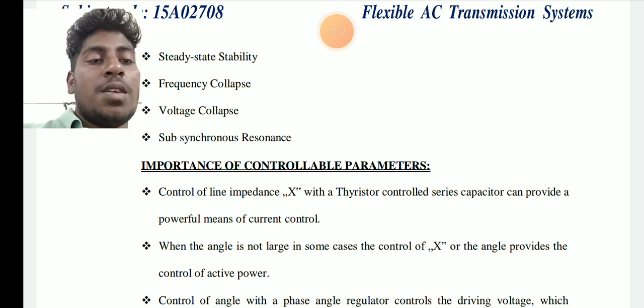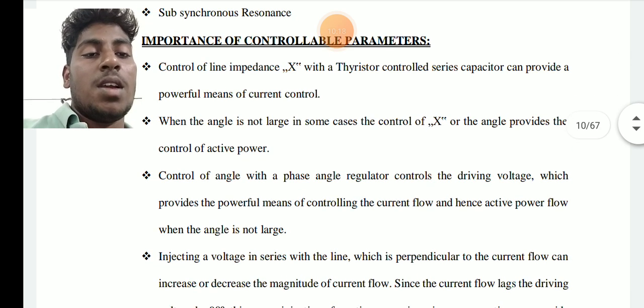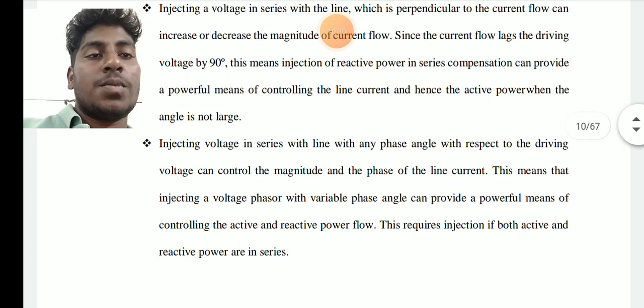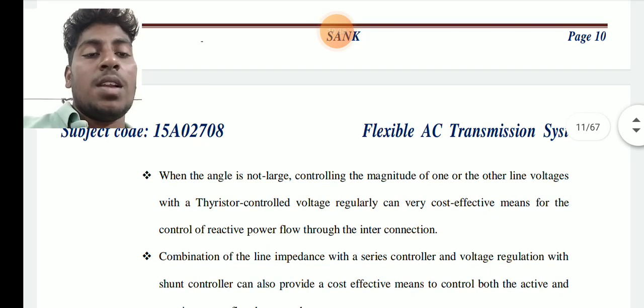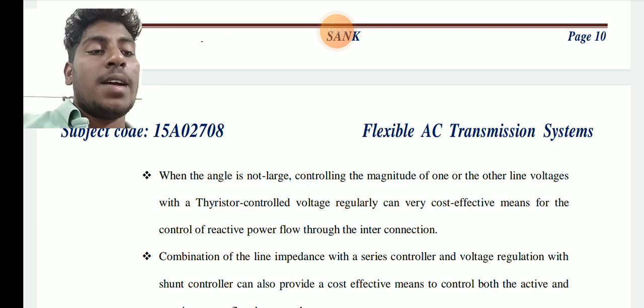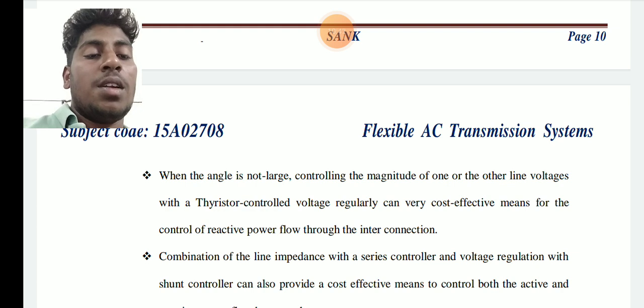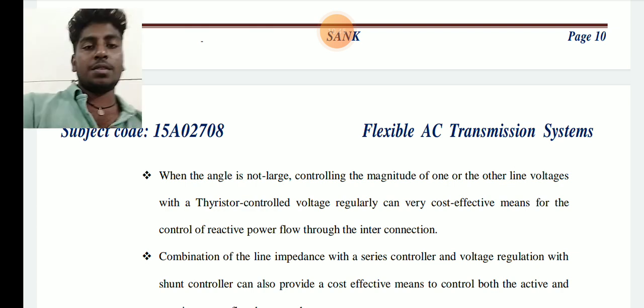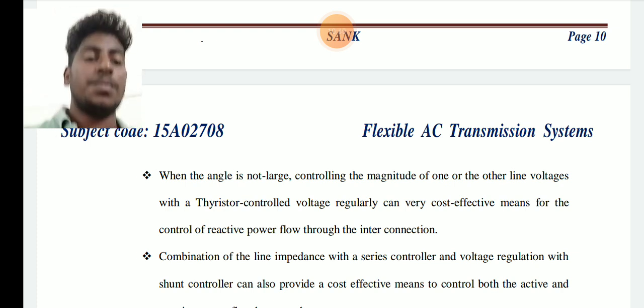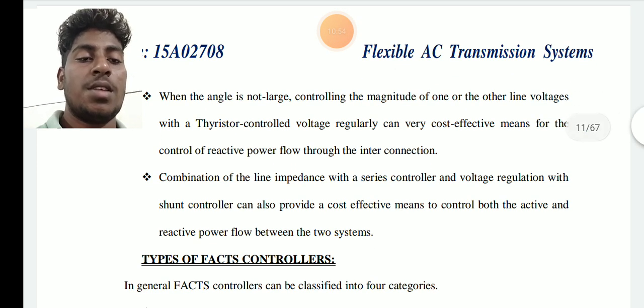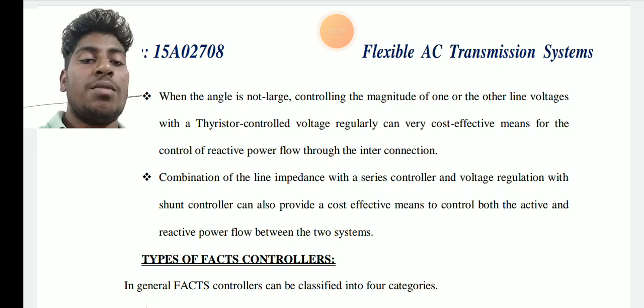Once I repeat, importance of controllable parameters. Controllable line impedance X with thyristor controlled series capacitors provides a powerful means of control. When the angle is not large, in some cases controlling X and the angle provides control of active power. Control of the angle with a phase angle regulator, and control of the driving voltage, provides a powerful means of controlling the current flow and hence the active power flow when the angle is not large. When the angle is not large, controlling the magnitude of one of the line voltages with a thyristor controlled voltage regulator can be a very cost effective means of control. Shunt controllers also provide a cost effective means to control both the active and reactive power flow between the two systems.